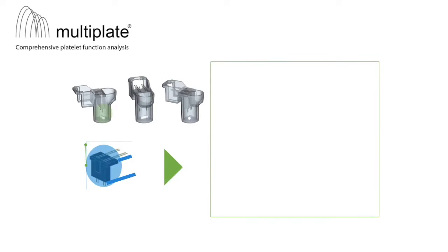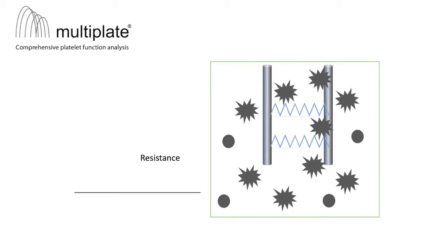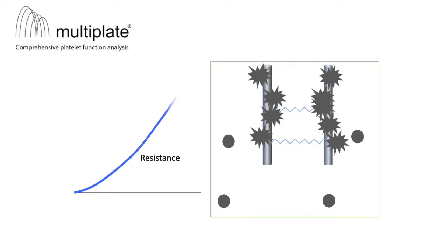Activated platelets adhere to and aggregate on the sensor wires. This leads to an increased resistance between the sensor wires, which is continuously recorded.